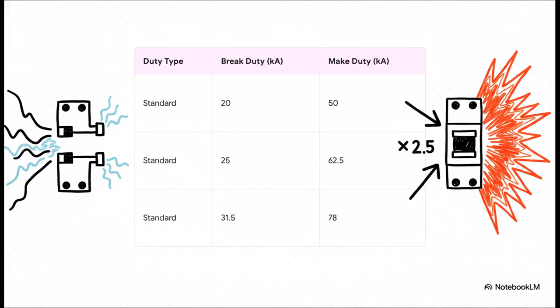Here's something really important to understand. A circuit breaker, the big switch that protects a circuit, actually has two different ratings. Its break duty is the fault current it can safely interrupt when it's opening. But its make duty is the much higher peak current it has to survive if it closes onto a fault that's already there. As you can see from the table, that make rating can be up to 2.5 times higher. That's a huge difference.